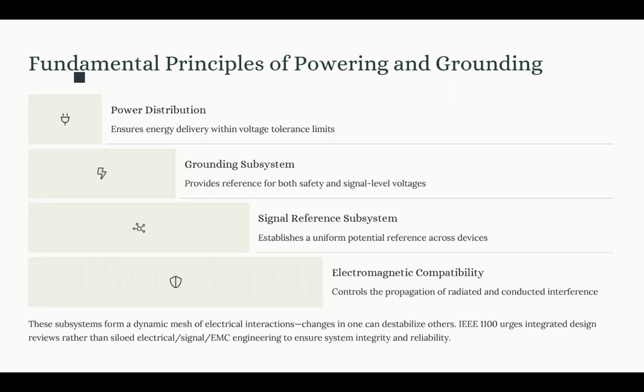We also have a requirement for bonding network interface, which is a single connection point between the SRG and the building grounding electrical system. So there is a requirement for that aspect of the grounding subsystems in the IEEE 1100. Now, the next subsystem is the signal reference. This basically establishes a uniform equipotential reference plane that is used for all the interconnected electronic equipment and makes sure of the signal integrity and the noise immunity.